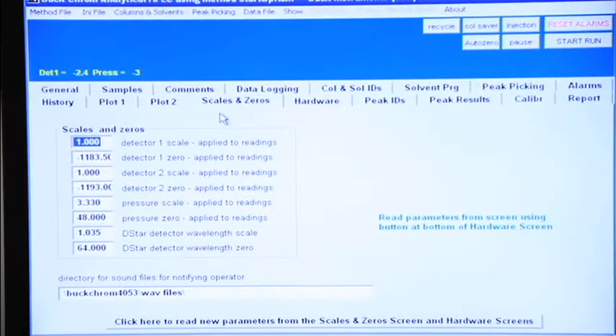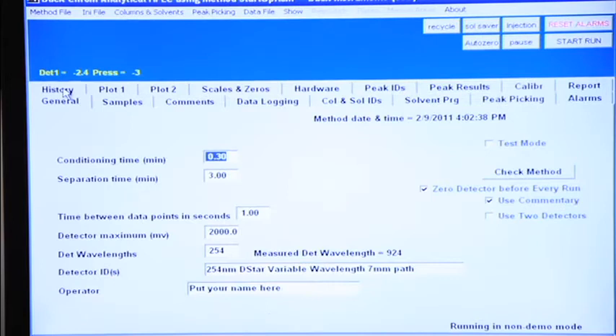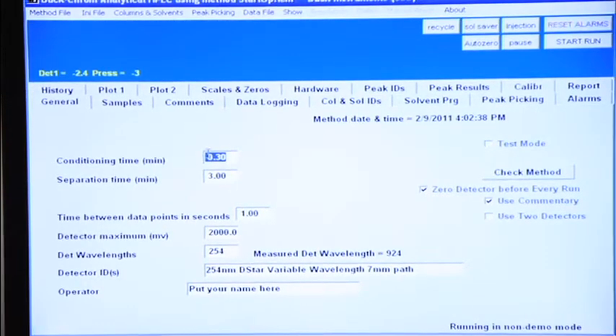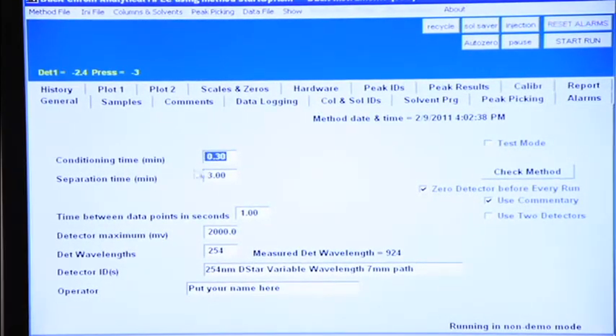Now that we're ready to run the HPLC, we're going to navigate to the General tab. Here you can set the conditioning time, which is the amount of time that the pump runs before a sample is injected, the separation time, which is the amount of time that the sample actually runs on the column for, the time between data points, which we generally recommend 1 second. The detector maximum will always be 2000 millivolts. You can also set the detector wavelength here. We're going to set it to 254 nanometers today.